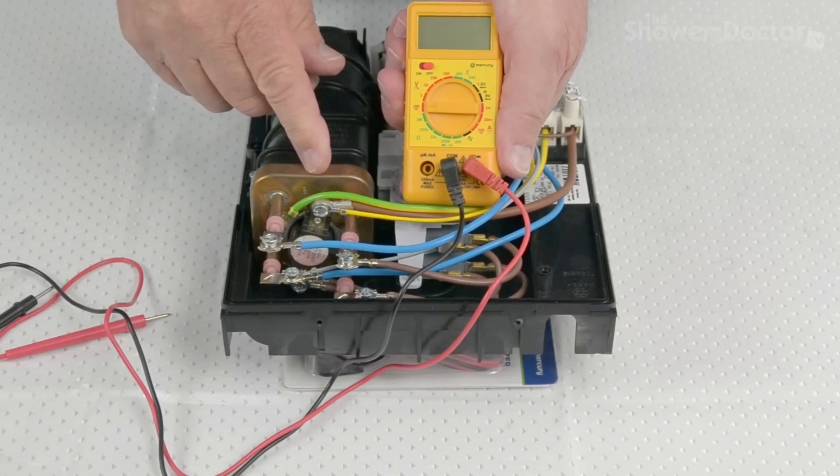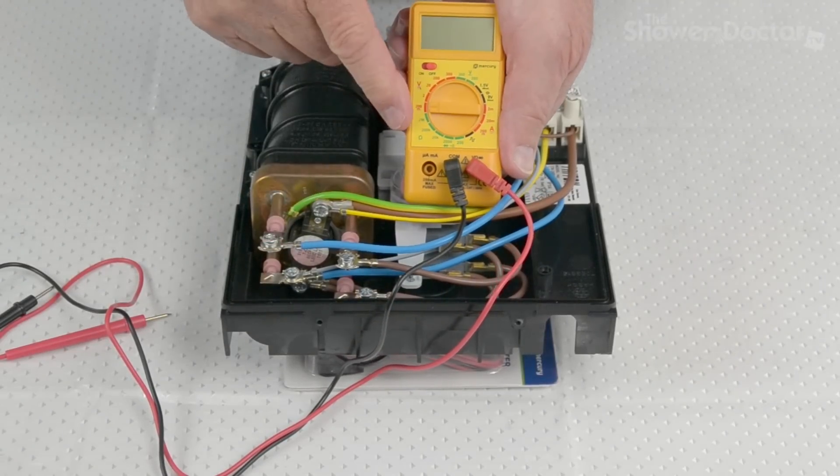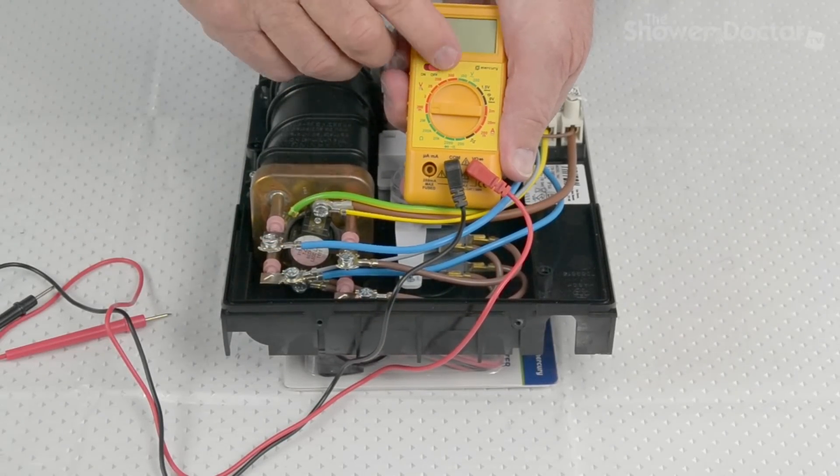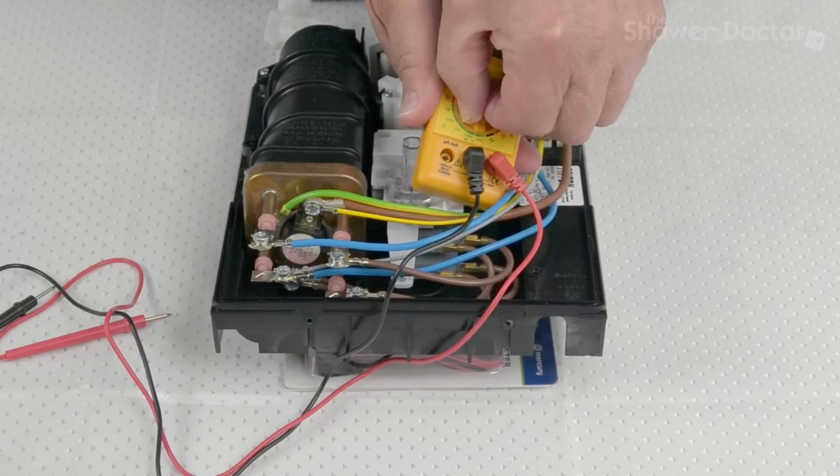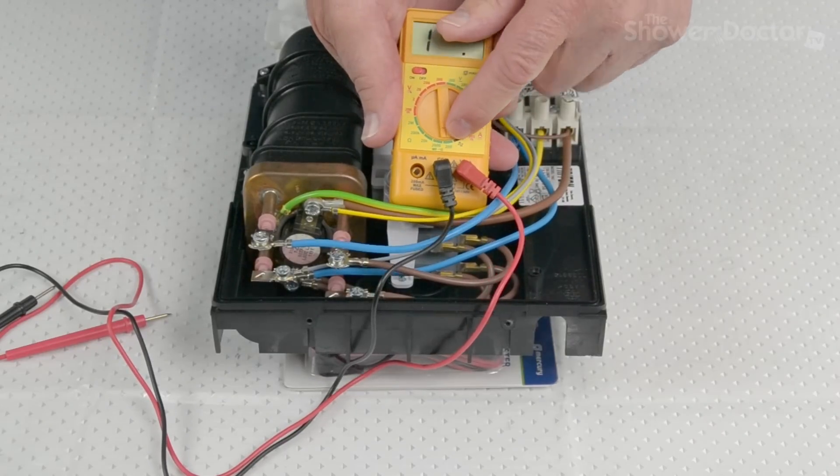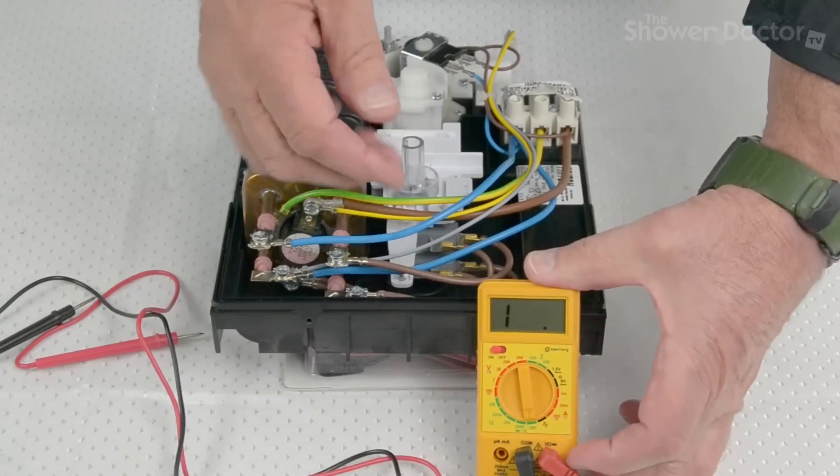In this test, we're going to test the resistance in the elements. So first of all, we need to set the meter. Turn it on. And it's not k ohms this time. It's just set for ohms. So down here, set for 200 ohms. And we test the elements.